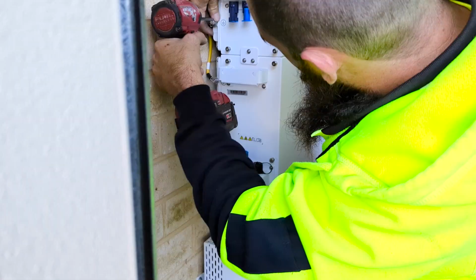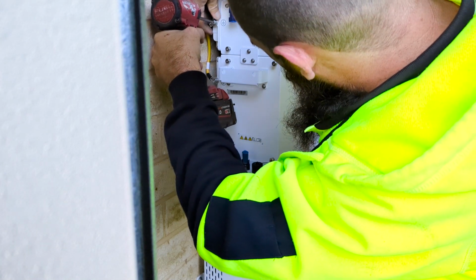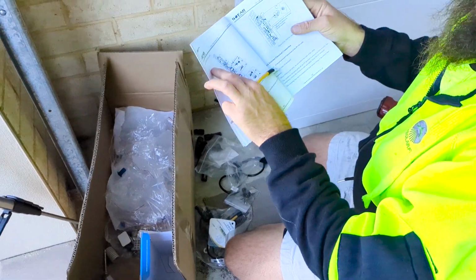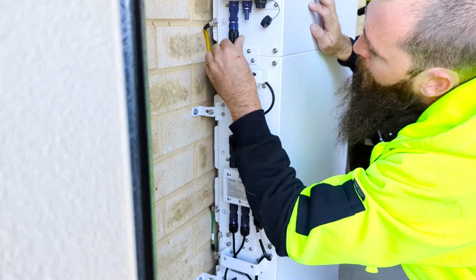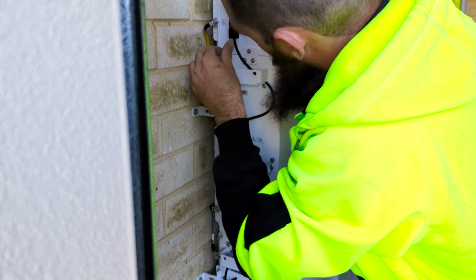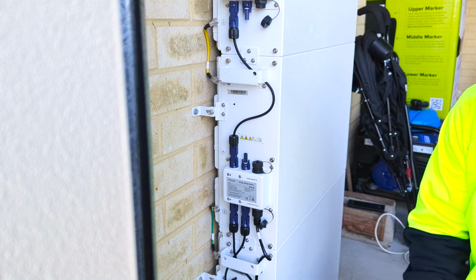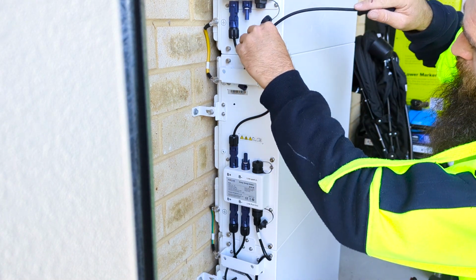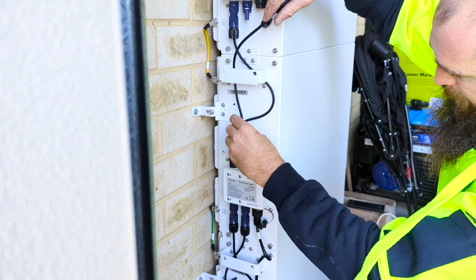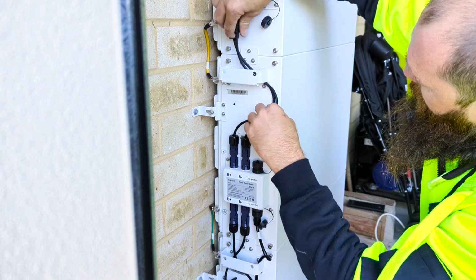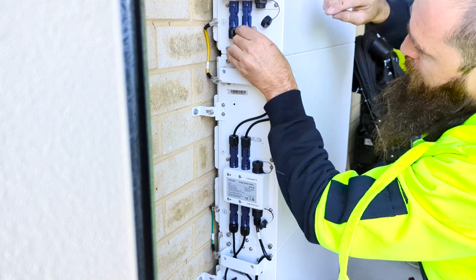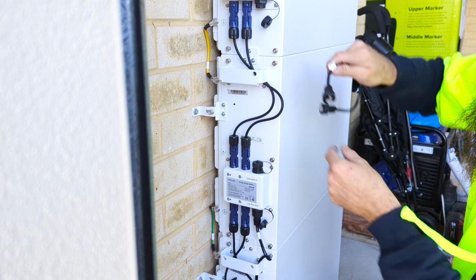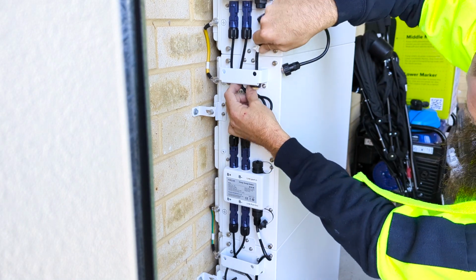Now we move on to the cabling, starting with the grounding cable, which you install as per the diagram in the user manual. Then connect the power ports of the inverter, BAT positive and BAT negative, to the cascading positive and negative power cables of the battery module, B positive and B negative. Connect the remaining battery modules from top to bottom and secure the cables with cable ties.